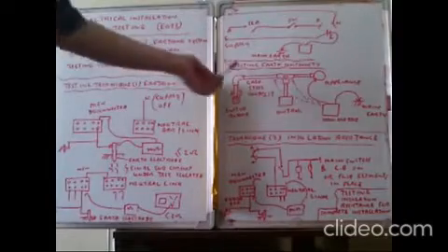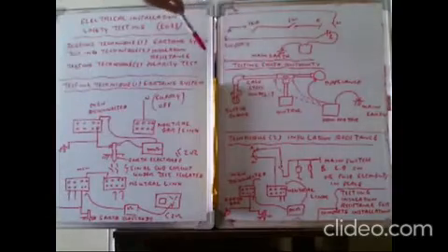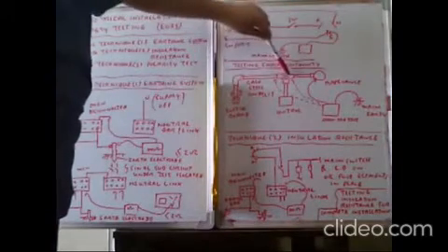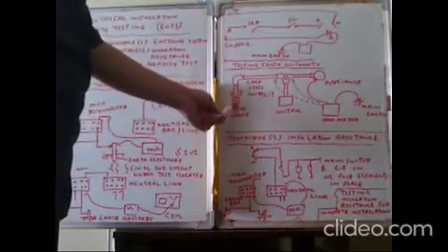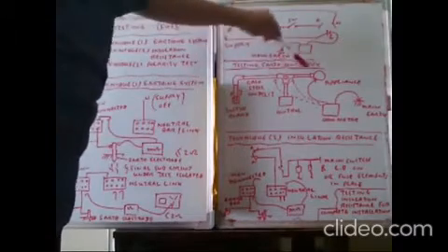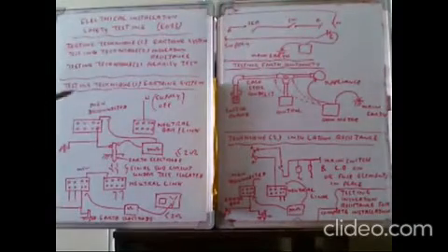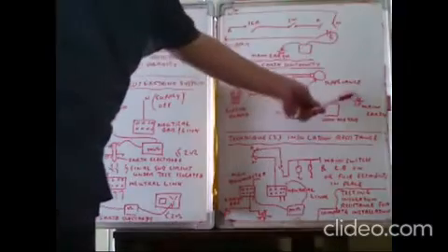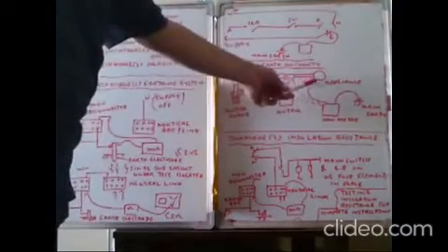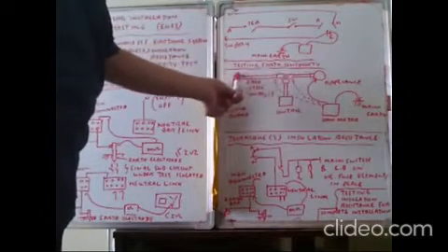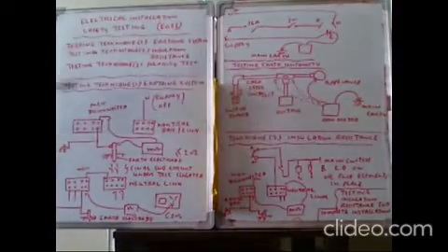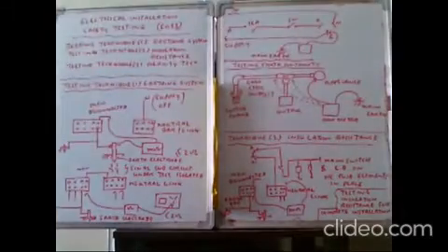We also need to test the earth continuity for steel conduit installations. The steel conduit acts as the earth conductor. The conduit is connected to the main switchboard and also to the appliance. Using an ohmmeter, connect one terminal to the main earth and another wire to the appliance conduit connection. All connections must be tested to ensure continuity of the earthing system.